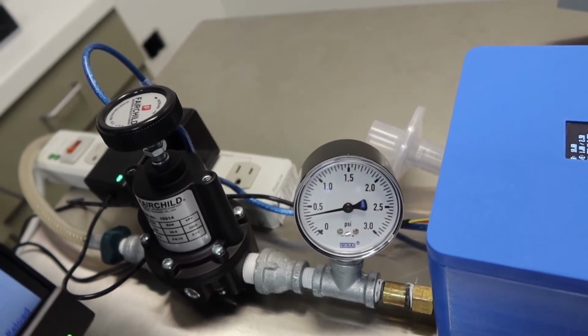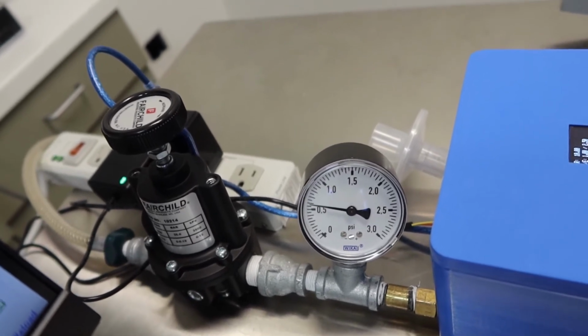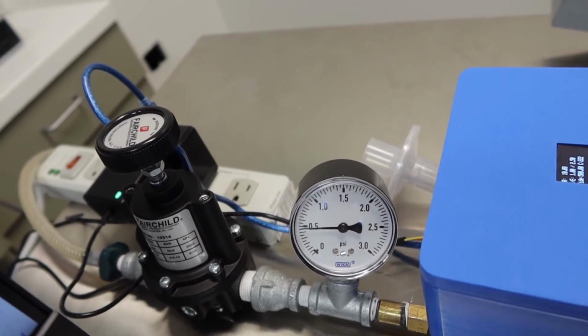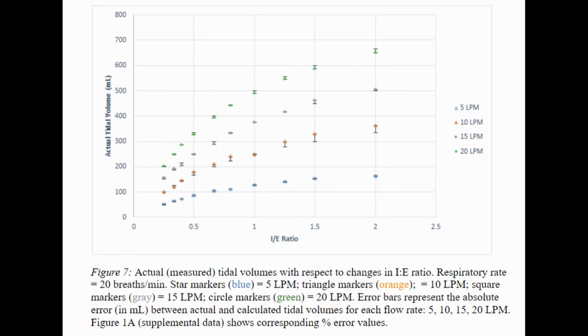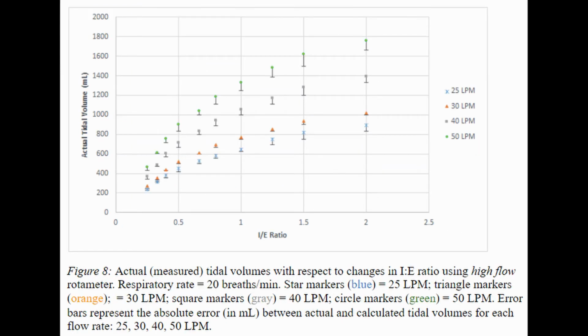And this happens as soon as air comes off the wall before it passes through the first inspiratory valve. In addition to optimizing the inspiratory-expiratory valve timing, we're able to adjust the inspiratory-expiratory ratios ranging from 2:1 to 1:4. With digital input, we can tell the ventilator exactly how much volume to deliver to the patient. We can do so with very high accuracy, and we can deliver tidal volumes ranging from 200 to 1,000 milliliters.